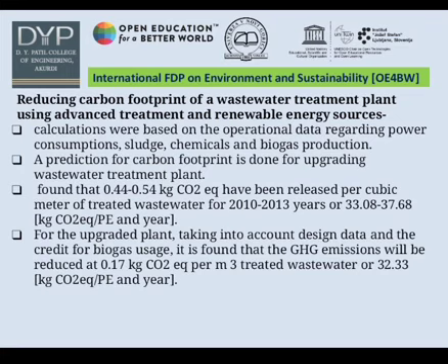In this slide, reducing the carbon footprint of a wastewater treatment plant using advanced treatment and renewable energy sources is discussed. The calculations were based on operational data regarding power consumption, sludge chemicals, and biogas production. For the upgraded plant, taking into account design data and the credit for biogas, it is found that GHG emissions will be reduced to 0.17 kg CO2 per cubic meter of treated wastewater, or 32.33 per year.